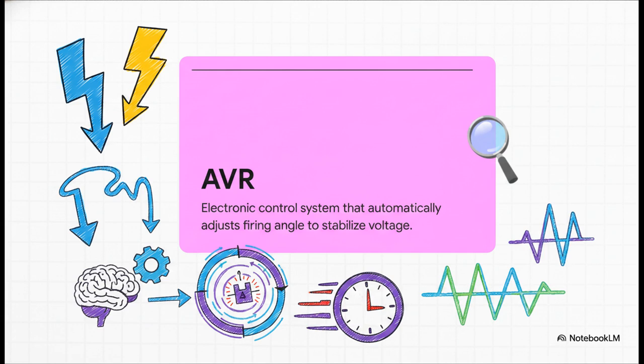This is done by the AVR, the Automatic Voltage Regulator. The AVR acts as a high-speed electronic brain for the whole operation. If it senses even a tiny drop in the generator's output voltage, it instantly adjusts the firing angle of thyristors, which you can think of as really high-speed electronic switches. This increases the DC current flowing into the rotor, which strengthens the magnetic field, which instantly boosts the voltage right back to normal. It reacts in fractions of a second to keep your power completely stable.